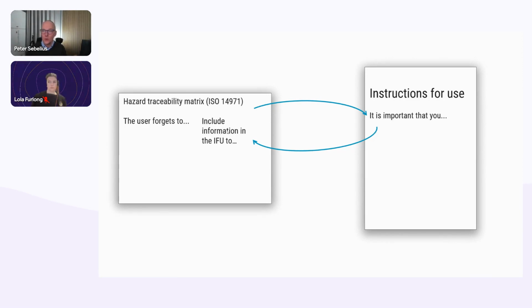Now, if you do not include it here, but you write it here, well, then you fail to identify all the hazardous situations. So then you're missing out on that requirement. And if you write it here and you don't have it in the IFU, well, then that's the other way around. You have identified the risk, but you didn't do the risk control measures. So you need to have both. And that is true for anything where if you don't follow the instruction or information, it results in harm. If you want to prove that this information is effective, keep in mind that this is most often done in your summative evaluation or human factors validation as part of the usability engineering process. So that's a good place to include that always, basically.